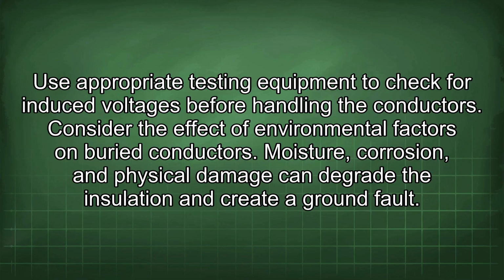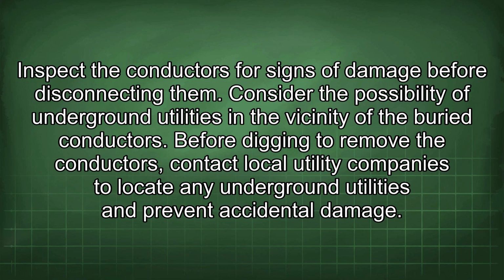Consider the effect of environmental factors on buried conductors. Moisture, corrosion, and physical damage can degrade the insulation and create a ground fault. Inspect the conductors for signs of damage before disconnecting them. Consider the possibility of underground utilities in the vicinity of the buried conductors. Before digging to remove the conductors, contact local utility companies to locate any underground utilities and prevent accidental damage.